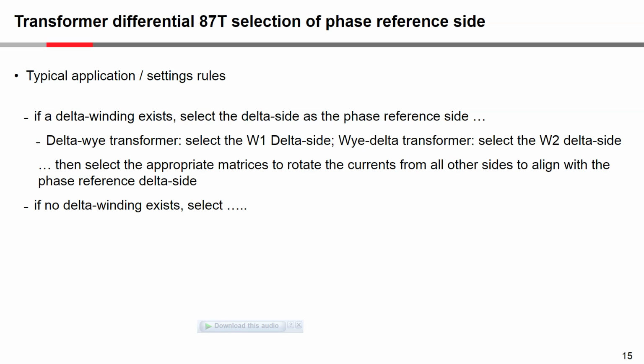So these are the kind of rules that you may be faced with. If a delta winding exists, select the delta side as the phase reference side. Okay, so if it's a delta Y transformer, then the phase reference should be the winding 1 side. If it's a Y delta transformer, then you should select the winding 2 side. Okay, and then of course for the other windings you would have to select the appropriate matrices. And if no delta winding exists, then some additional rules follow.